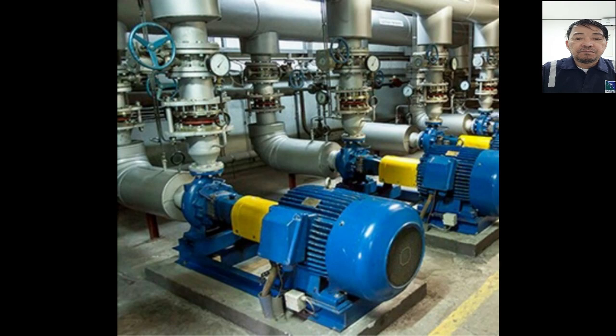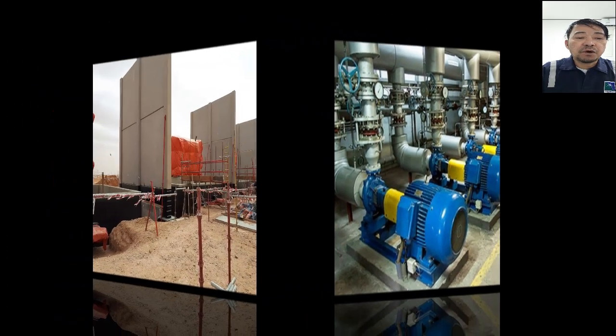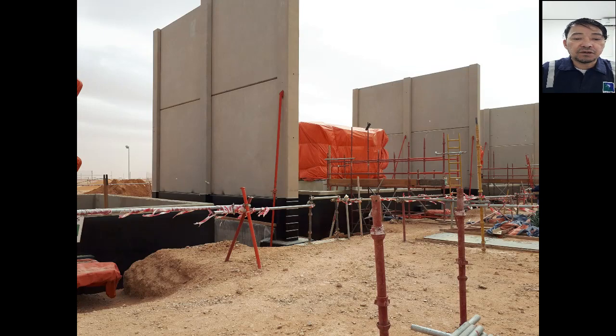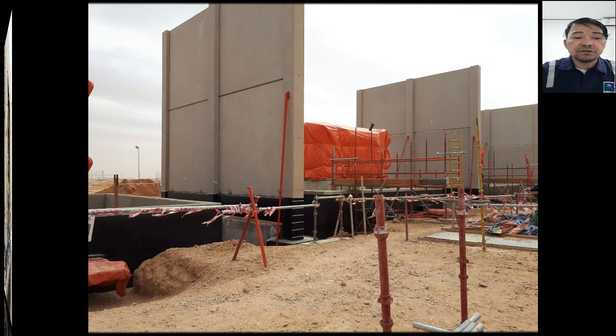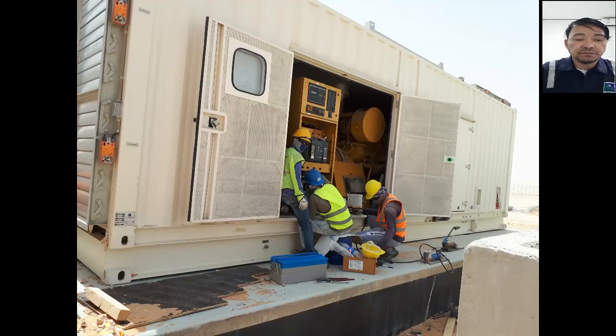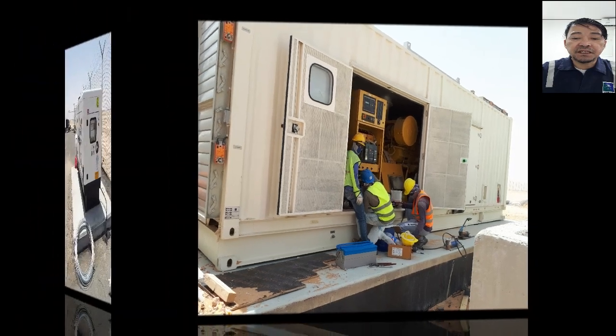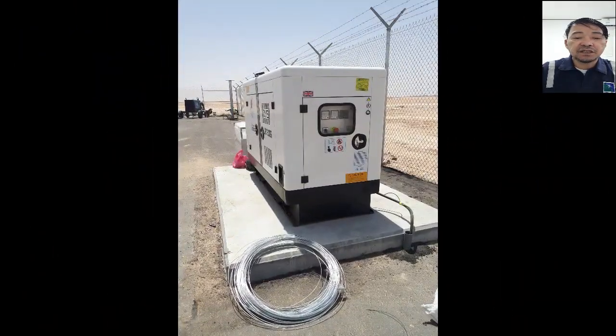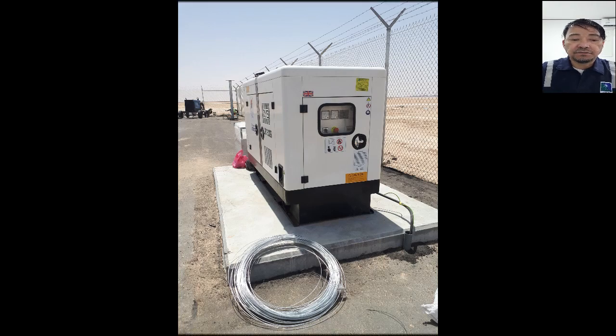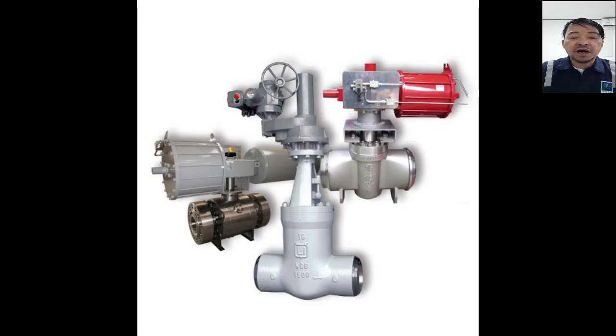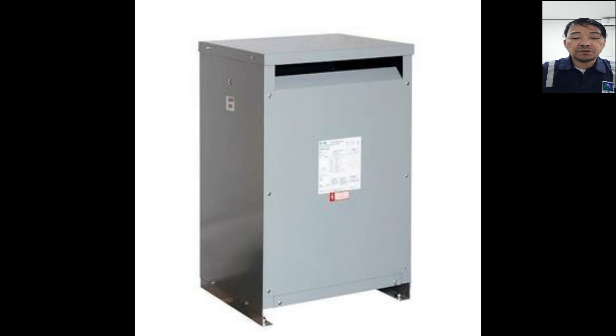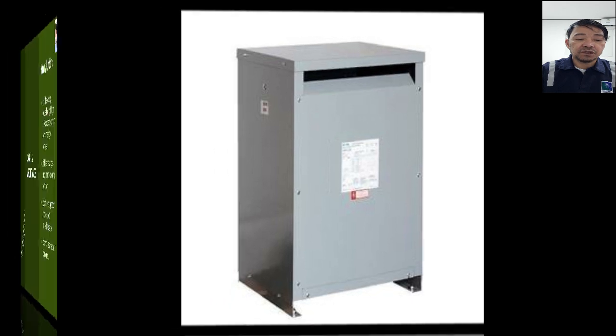Frames of equipment, motors, generators, and transformers operating at 1000 volts or greater shall have two connections to the grounding electrode. Motors, transformers, and generators operating at a nominal voltage of 480 volts shall have a minimum of one connection to the grounding electrode. Motor-operated valves, lower voltage motors, and transformers are grounded through the associated EGC, or the equipment grounding conductors.